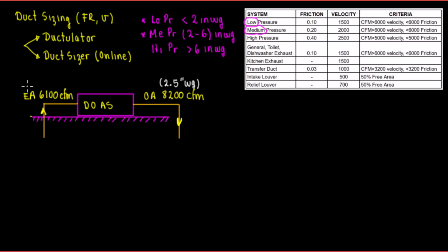And then for this one, it is going to be exhaust, depending on your ductwork, 1.5 inches of water gauge. This is preliminary. Once you get the selections from the representative, for example, Trane, AAON, Carrier, once you get all the selections and everything, you have to run a static pressure calculation, all the ductwork, all the elbows, adding all that up, and you can validate these assumptions, this preliminary design.